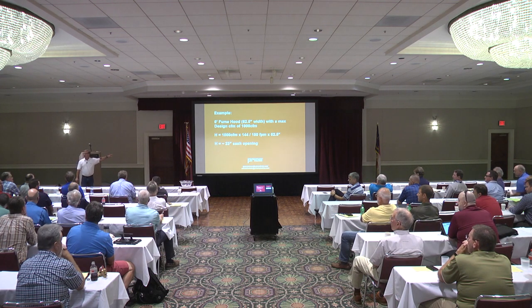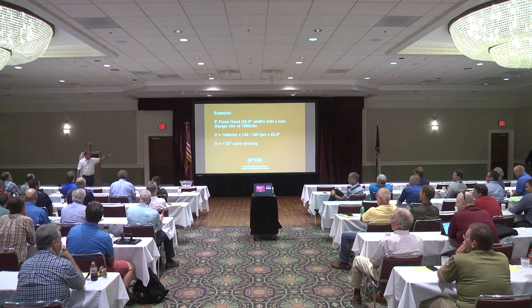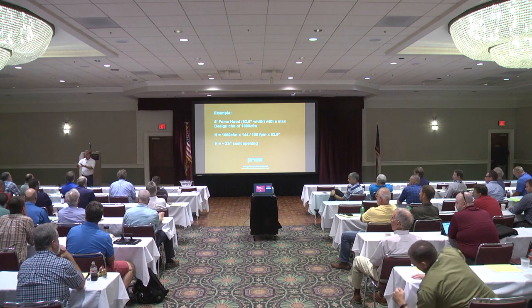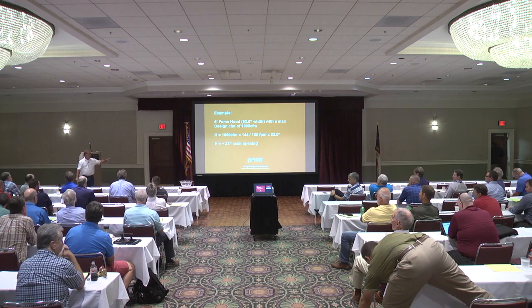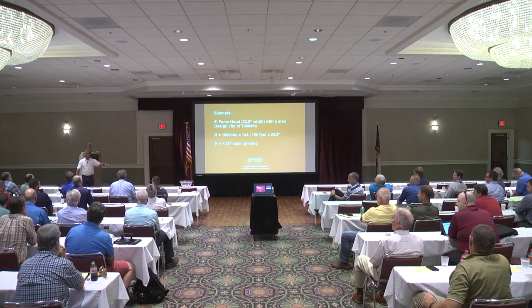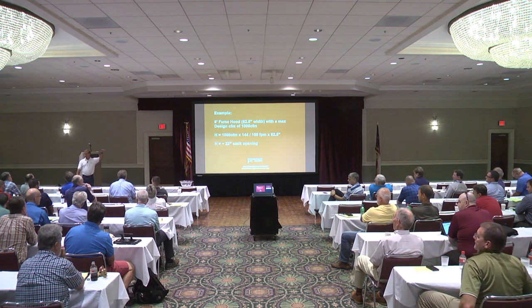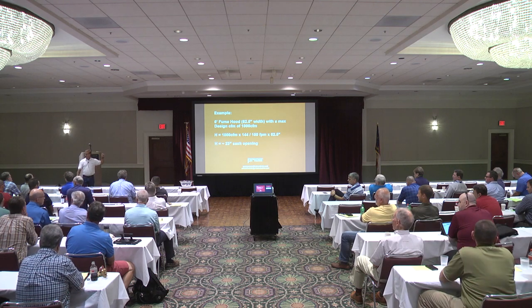And you're not going to do that in a VAV hood. A VAV hood is going to maintain 100 feet per minute by its design, by what it's supposed to do, at any sash height between minimum design CFM and maximum design CFM. So if you find your maximum sash height.